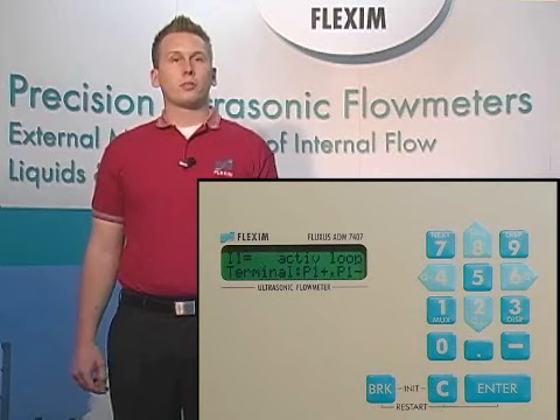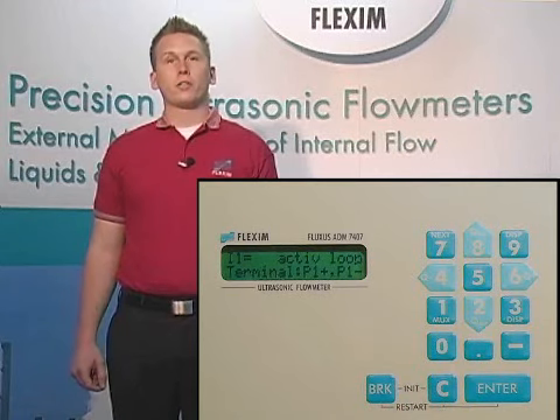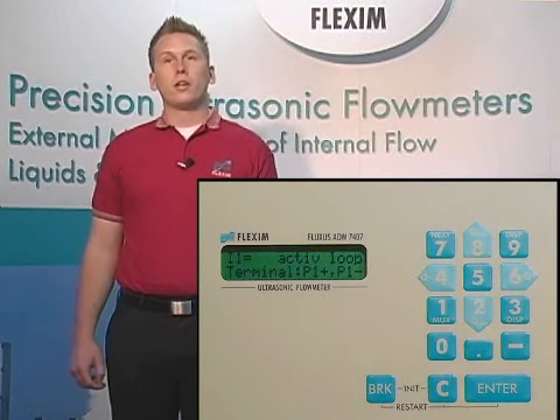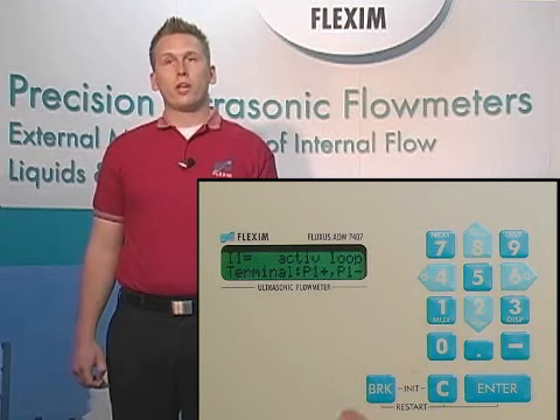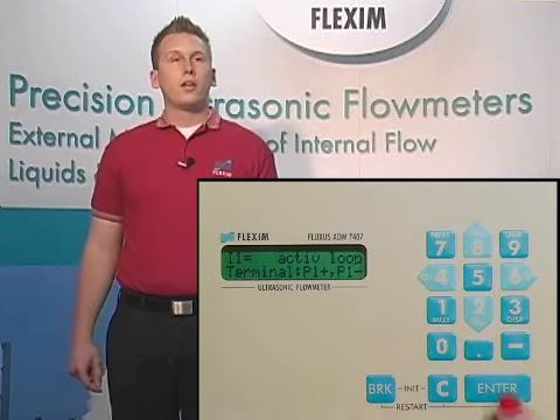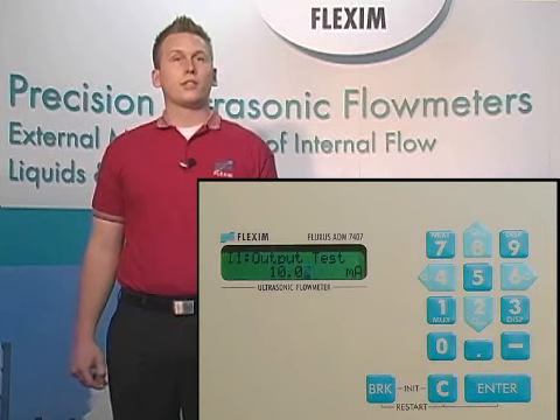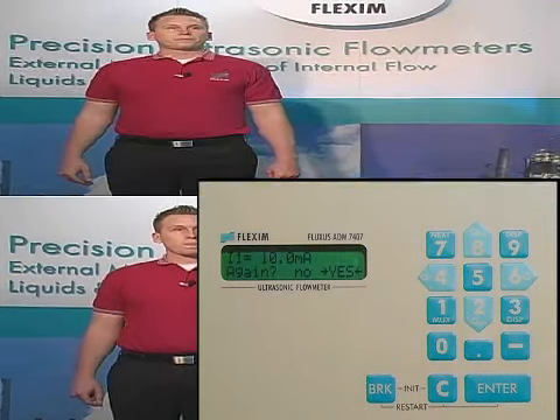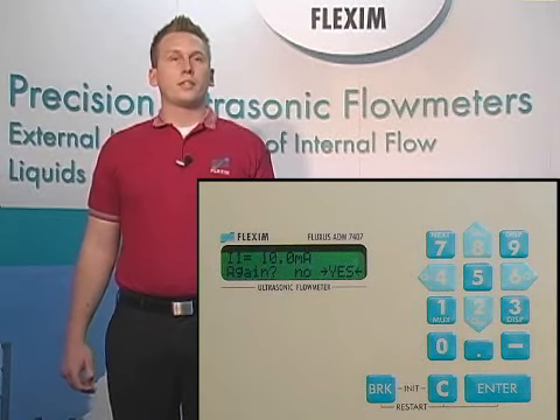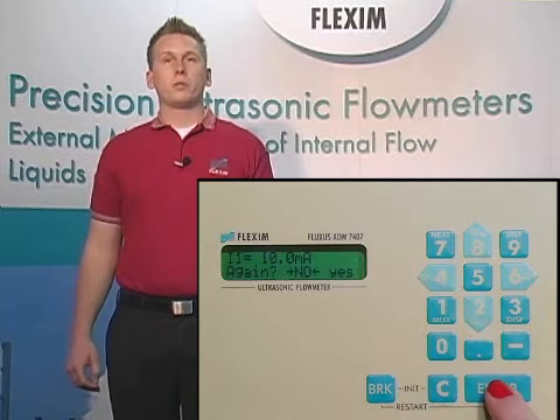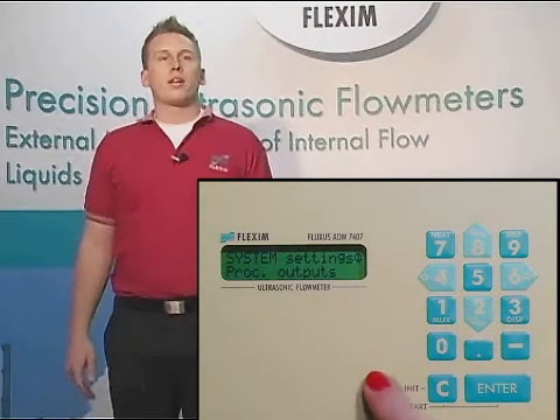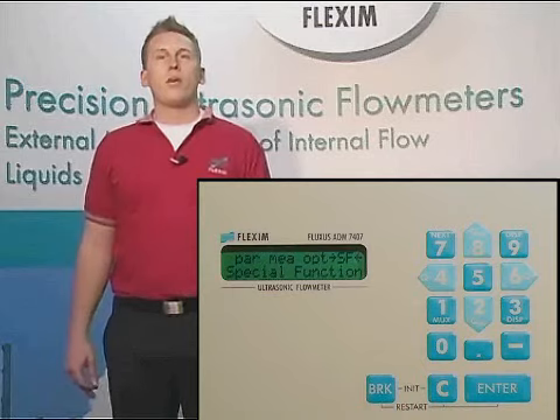The meter now tells us where to physically plug in our 4 to 20 wires to the meter. For I1, this is always on P1 plus and P1 minus. Hitting enter now allows us to test the signal if we'd like. And now choosing not to test again, we're back to the main process outputs menu. Hitting break has brought us back to the main screen, and now ready to begin a measurement with our meter.